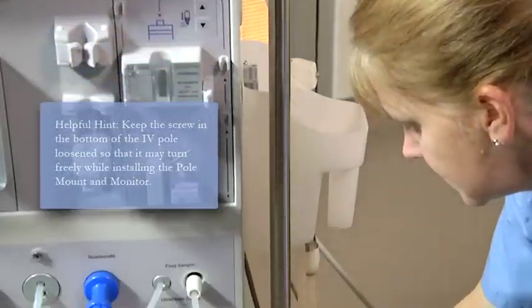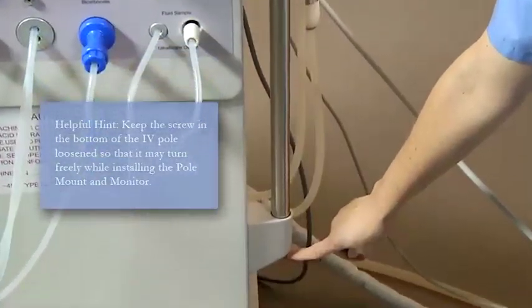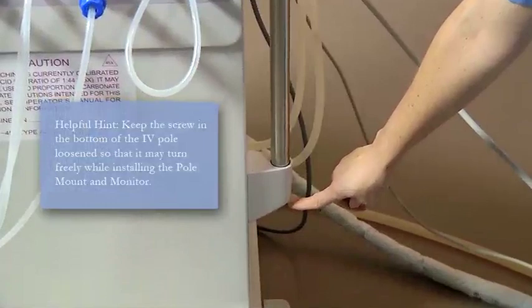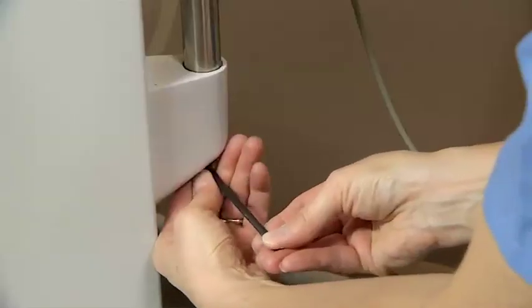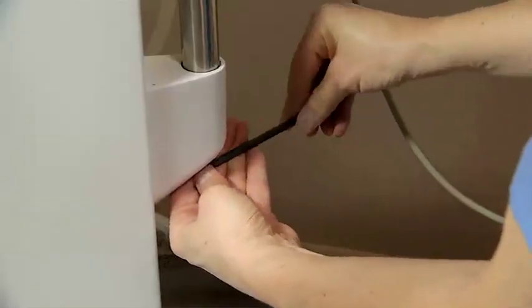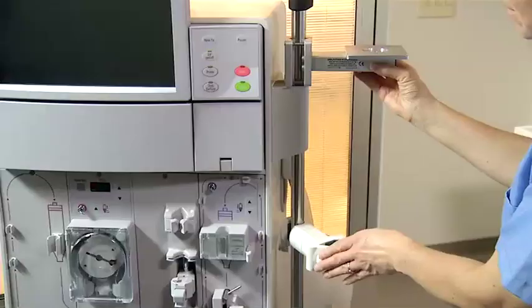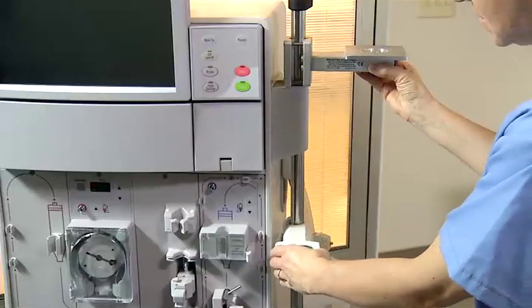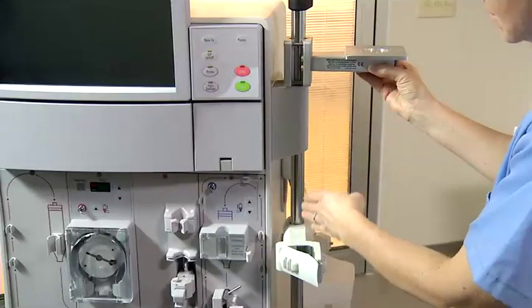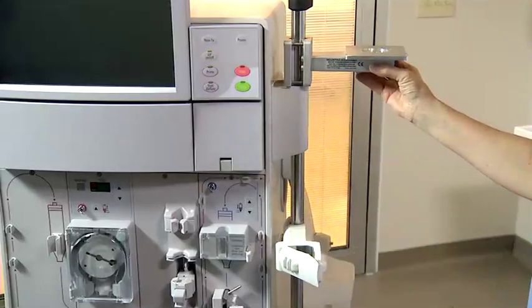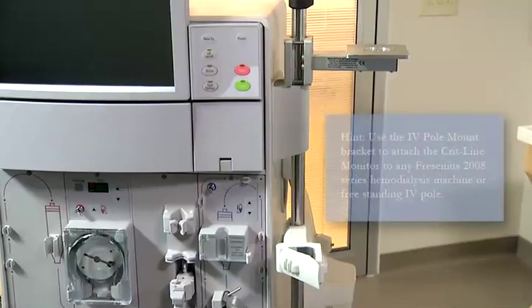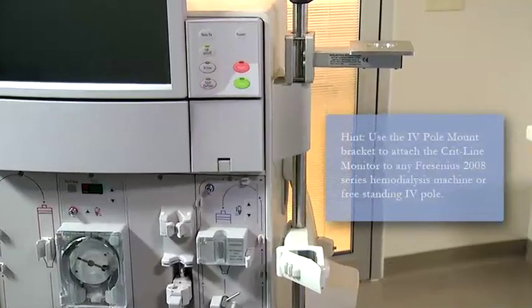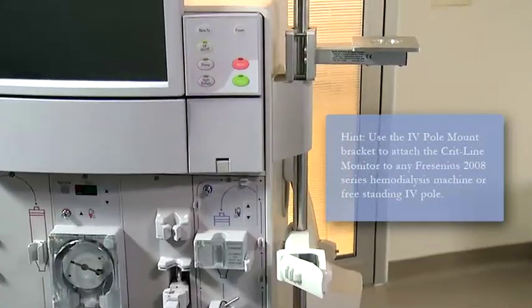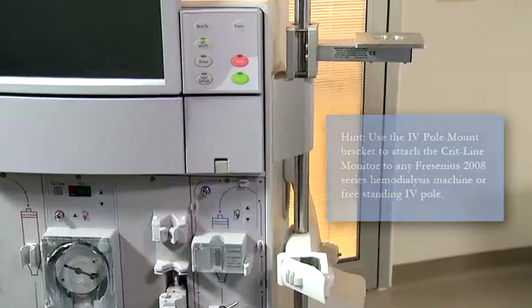It's helpful to keep the screw in the bottom of the IV pole loosened to allow the pole to move freely while installing the pole mount and monitor. Tighten the screw once the monitor and dialyzer holder are aligned properly. Never place the CritLine monitor on top of the hemodialysis machine. The IV pole mount bracket can be utilized on a freestanding IV pole. Simply follow the instructions as noted.